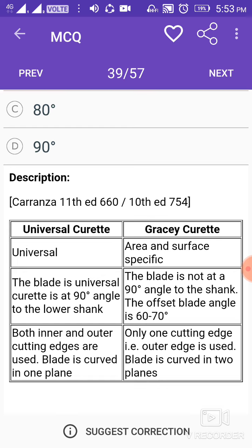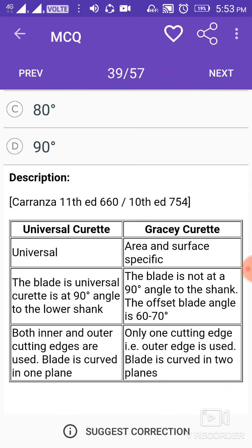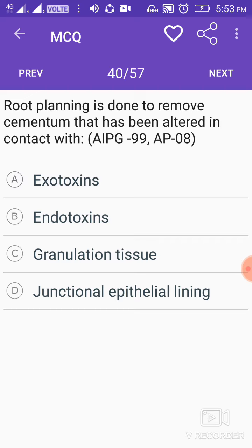Universal curettes are universal, while Gracey curettes are area- and surface-specific. In the universal curette, the blade is at a 90-degree angle to the lower shank, and both inner and outer cutting edges are used; the blade is curved in one plane. In the Gracey curette, the blade is not at a 90-degree angle to the shank — the offset blade angle is 60 to 70 degrees — only one cutting edge (the outer edge) is used, and the blade is curved in two planes.